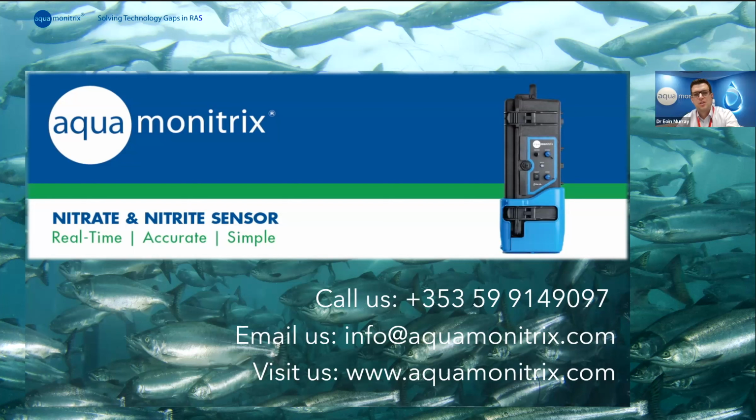I see there's a question around ISO performance. I think that's an important point. We recently obtained an ISO accreditation for the analyzer for performance. It's the ISO 14034 around online analyzers, and it was in a wastewater application, but a very long process as all accreditation processes are. At the moment, to the best of our knowledge, we're the only commercially available analyzer that has an ISO accreditation for performance on nitrate monitoring.